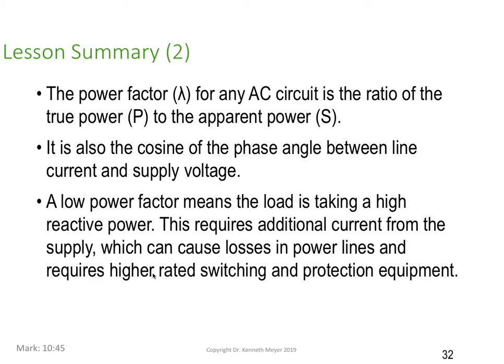Power factor for any AC circuit is the ratio of the power to the apparent power. So if you've got the power and you have the apparent power, you can work out the power factor. It's also the cosine of the phase angle between line current and supply voltage. A low power factor means that the load is taking a high reactive power. This requires additional current from the supply, which can cause losses in the power lines and requires higher rated switchgear and protection equipment. So you get heat losses, I squared R losses, and your transformers and your generators have to be big enough to carry the apparent power.